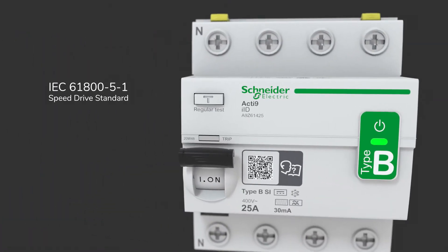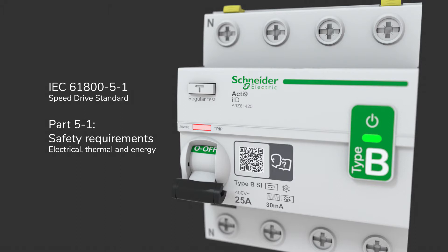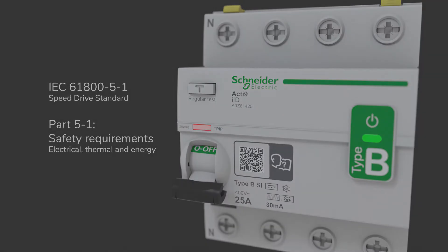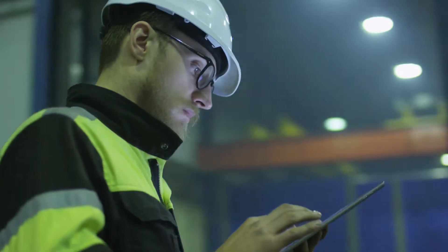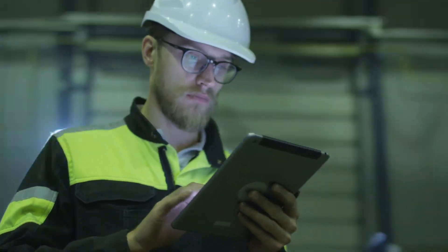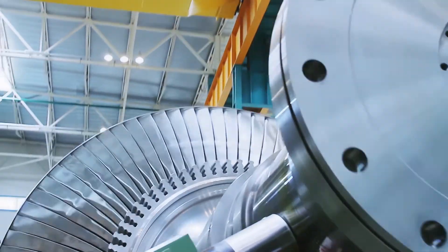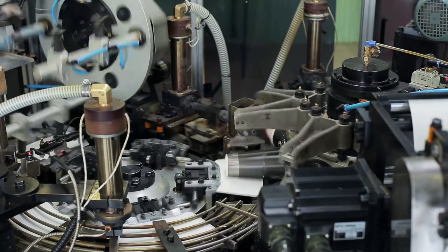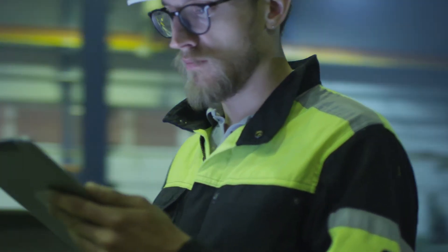Schneider Electric has developed a new Acti9 B SI type RCCB. This is the same type as recommended by the latest IEC standard for speed drives. When operating motors with speed drives, they can produce DC and high-frequency AC leakage currents that cannot be detected by A type RCCBs alone. BSI type technology is designed to detect these types of currents and protect people.